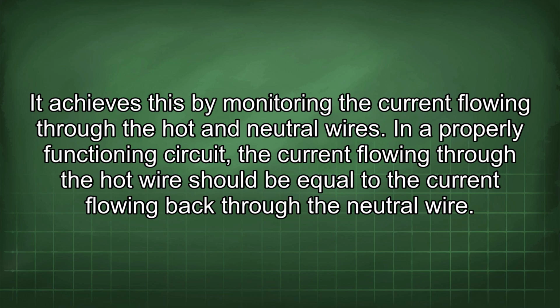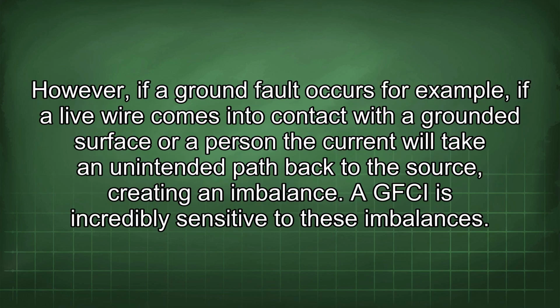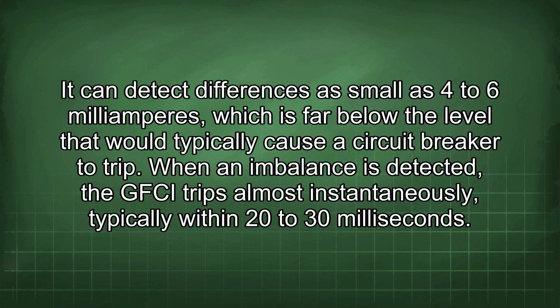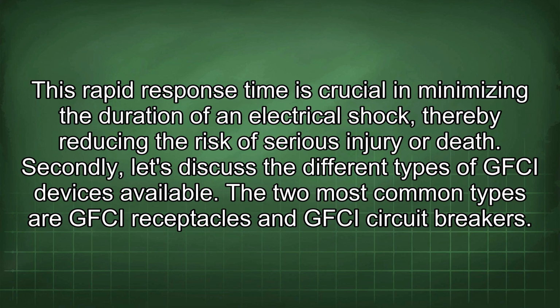In a properly functioning circuit, the current flowing through the hot wire should be equal to the current flowing back through the neutral wire. However, if a ground fault occurs, for example, if a live wire comes into contact with a grounded surface or a person, the current will take an unintended path back to the source, creating an imbalance. A GFCI is incredibly sensitive to these imbalances. It can detect differences as small as 4 to 6 milliamperes, which is far below the level that would typically cause a circuit breaker to trip. When an imbalance is detected, the GFCI trips almost instantaneously, typically within 20 to 30 milliseconds. This rapid response time is crucial in minimizing the duration of an electrical shock, thereby reducing the risk of serious injury or death.